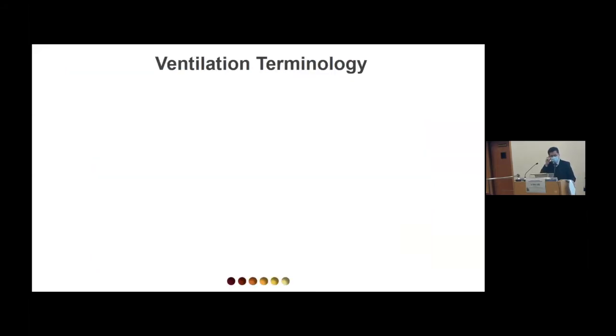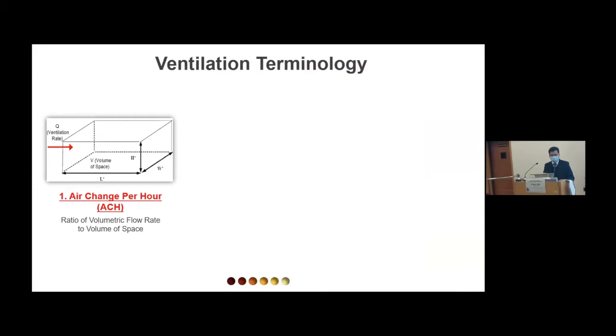So before going forward, I would like to share with you some of the common terminology found in discussing ventilation systems. The first term is air change per hour, or sometimes we call it ACH in short. The meaning of this is very straightforward. It is the ratio of the volume of outdoor air flowing into a given space in an hour divided by the volume of that space.